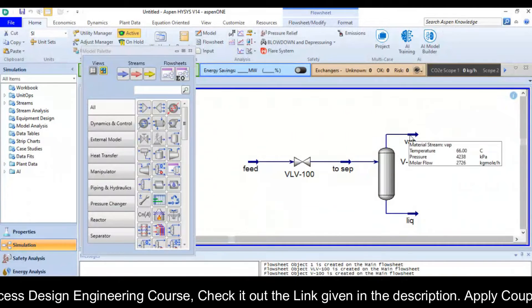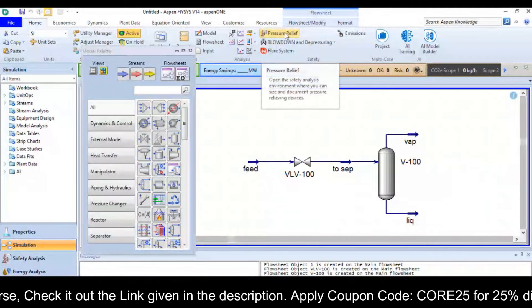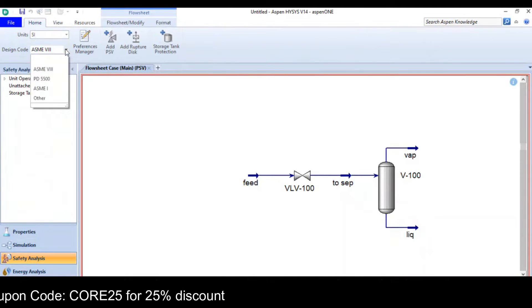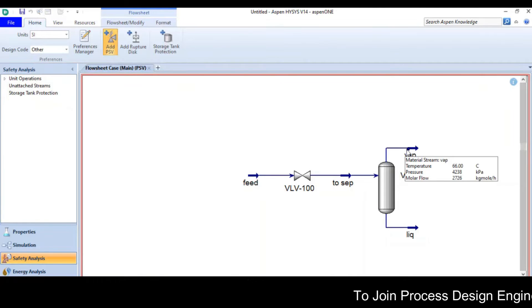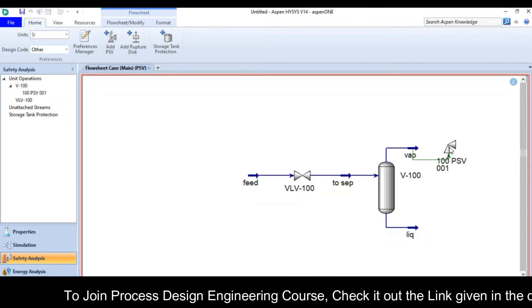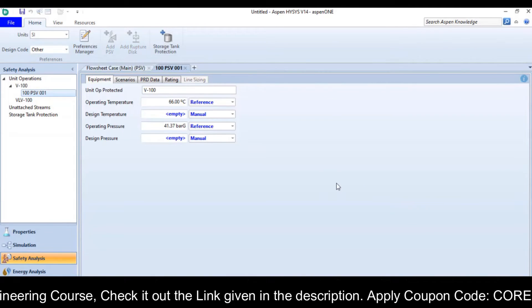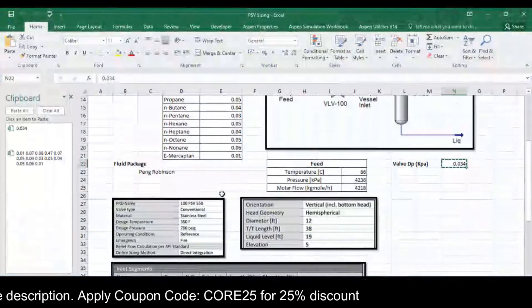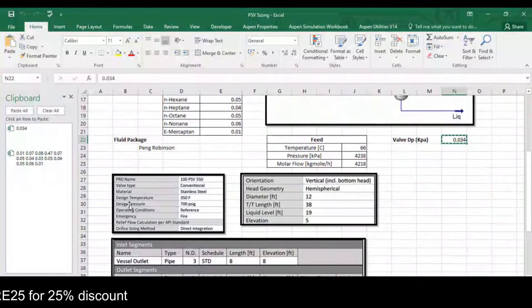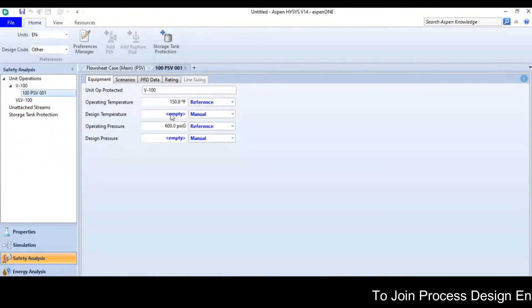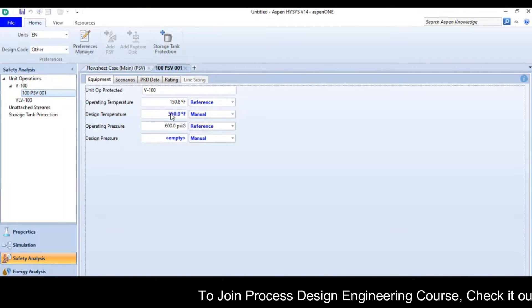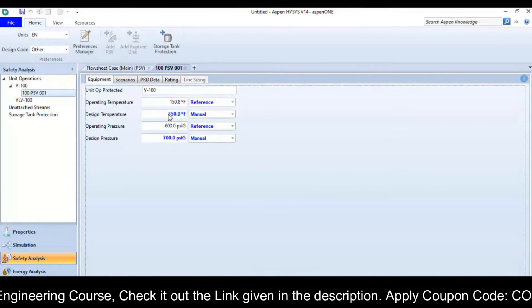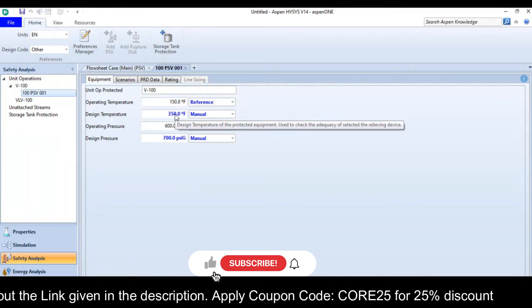In order to put a PSV on the vapor stream, you can click on pressure relief option or either go to safety analysis. If you are using API code it will be better to use other and then click on the add PSV button and go near the vapor outlet and click here to place the PSV. Now double click the PSV and provide the design temperature and pressure. In my case the design temperature is 350, pressure is 700 PSI.